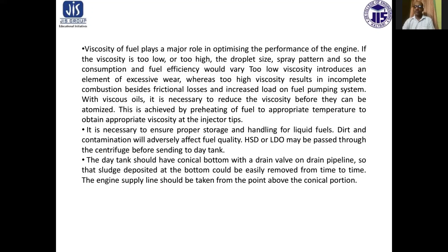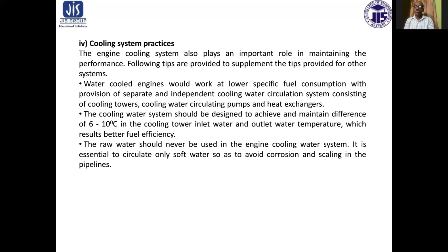Number 4, cooling system practice. The engine cooling system also plays an important role in maintaining the performance. The following tips are provided to supplement the tips provided for other systems. Water-cooled systems would work at lower specific fuel consumption, with provision of a separate and independent cooling water circulation system consisting of cooling towers, cooling water circulating pumps and heat exchangers. The cooling water system should be designed to maintain a difference of 6 to 10 degrees centigrade between cooling tower inlet water and outlet water temperature, which results in better fuel efficiency. Raw water should never be used in the engine cooling water system. It is essential to circulate only soft water so as to avoid corrosion and scaling in the pipeline.